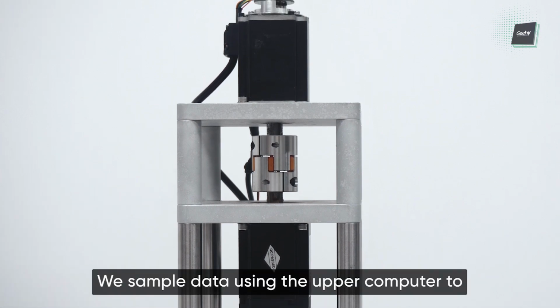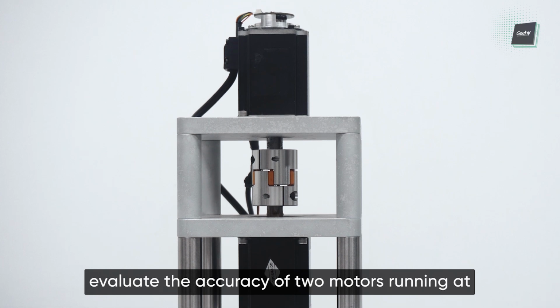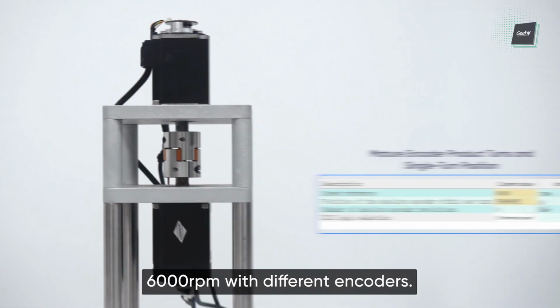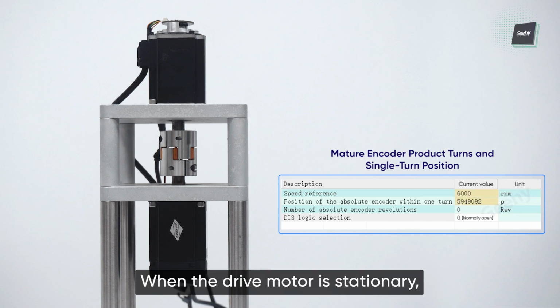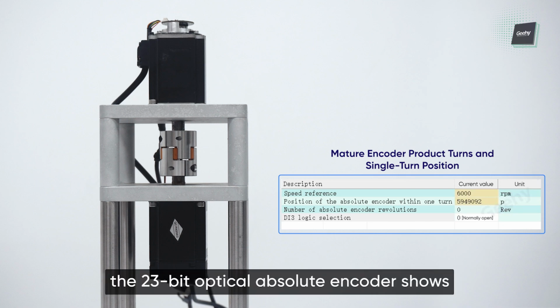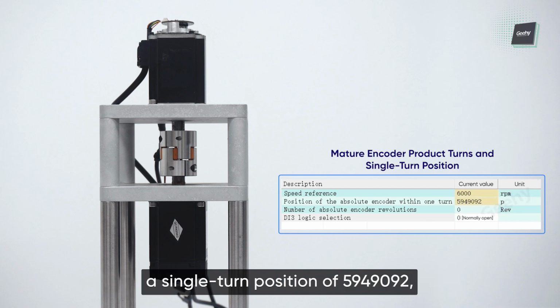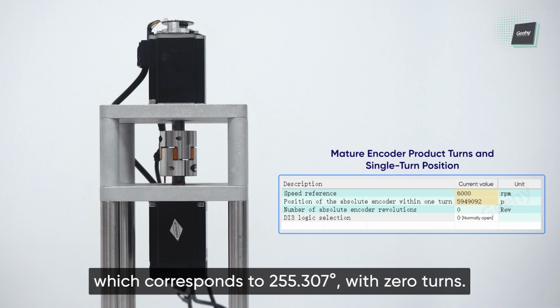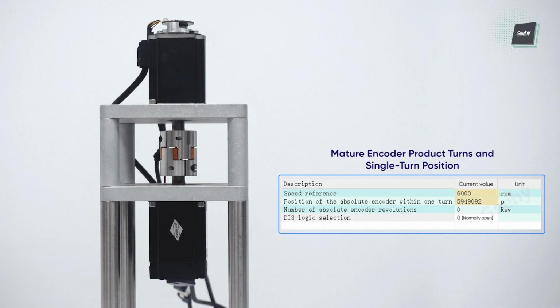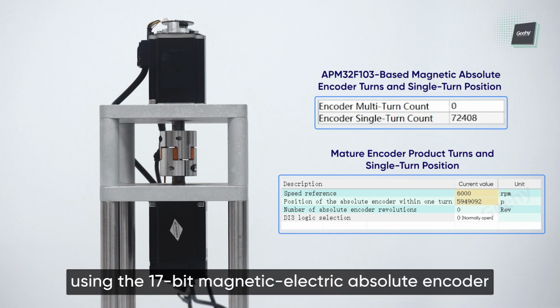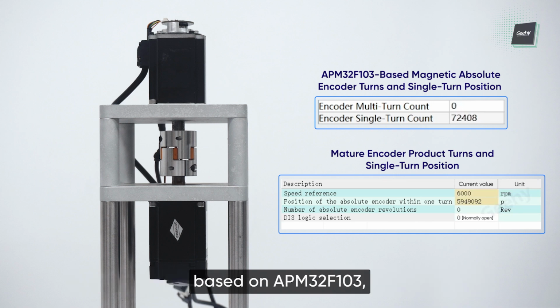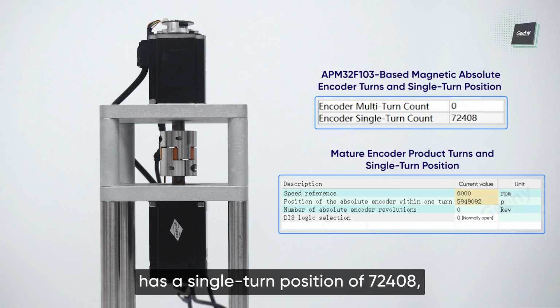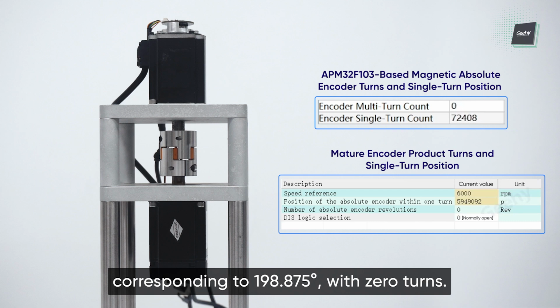We sample data using the upper computer to evaluate the accuracy of 2 motors running at 6,000 revolutions per minute with different encoders. When the drive motor is stationary, the 23-bit optical absolute encoder shows a single turn position of 5949092, which corresponds to 255.307 degrees, with 0 turns. The load motor, using the 17-bit magnetic electric absolute encoder based on APM32F103, has a single turn position of 72408, corresponding to 198.875 degrees, with 0 turns.